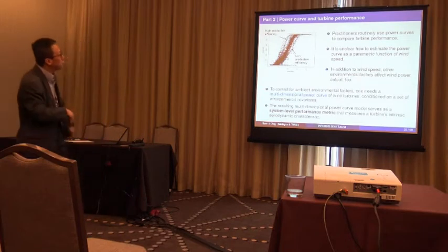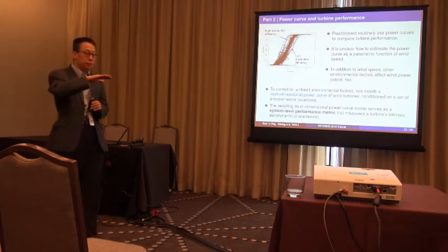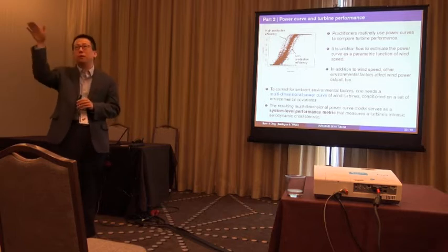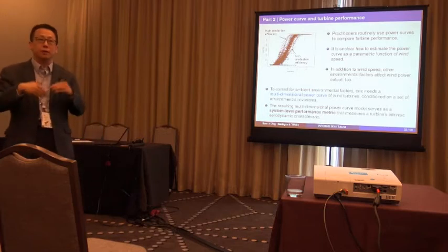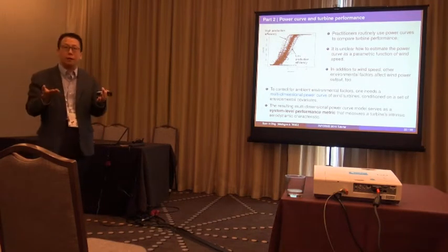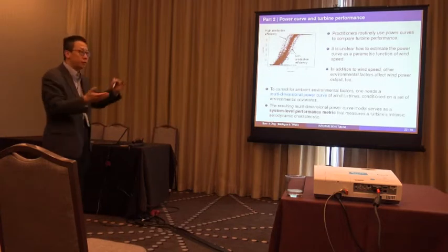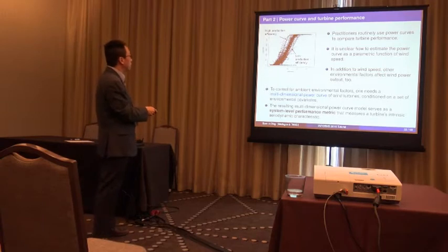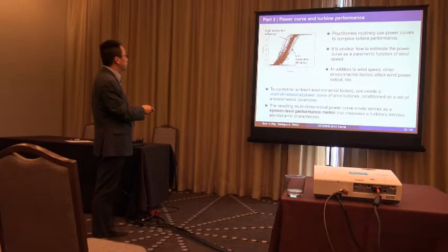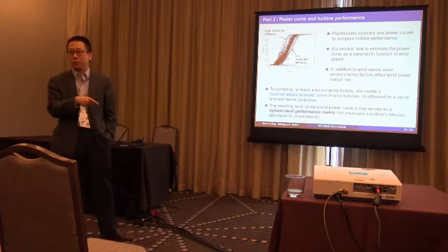So this is a problem related to the power curve. As I mentioned, that very nice, clean, thin power curve, usually called the nominal power curve from the OEM, never really materialized in reality. In reality, it's always messier, and the data you have has much wider variability. For example, if you take 10-minute wind speed, this particular wind turbine can produce wind power pretty much from 500 kilowatts all the way to nearly the top. We purposely hide the top because that's one of the proprietary pieces of information we're not supposed to release.